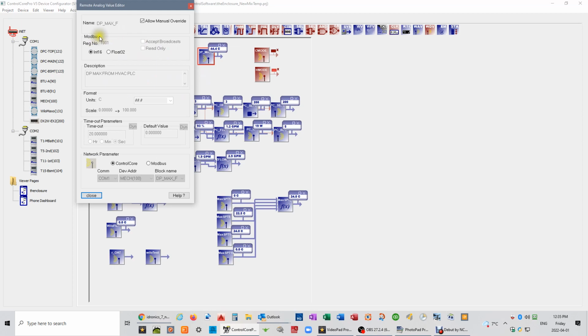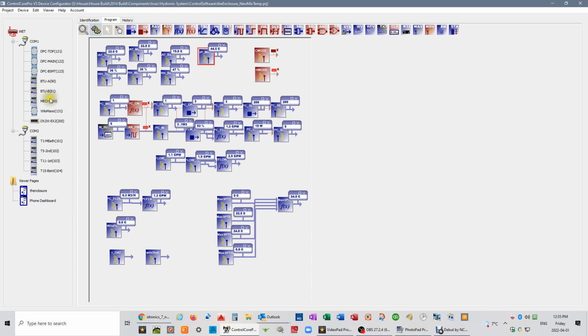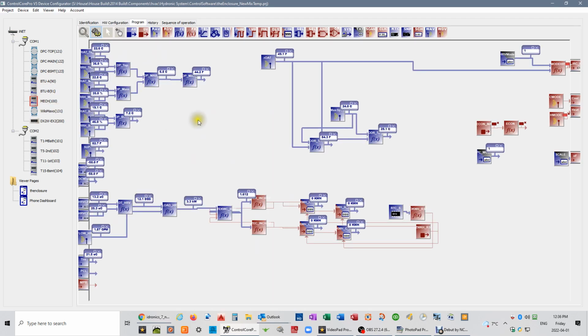So here you can see the maximum dew point from the HVAC PLC. And if we go down to the HVAC PLC, which is, I think, this one here, we can see that we've remotely called the blocks that we've created on iNet, which remotely called the parameters of the 3 dew point sensors. We then are creating the dew point for each of those. So we have the top floor dew point is 6.8 Celsius, the main floor is 7, and the basement is 7.2, and these are based on temperatures 22.6 and 36.